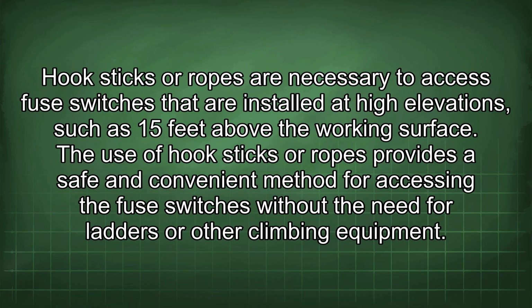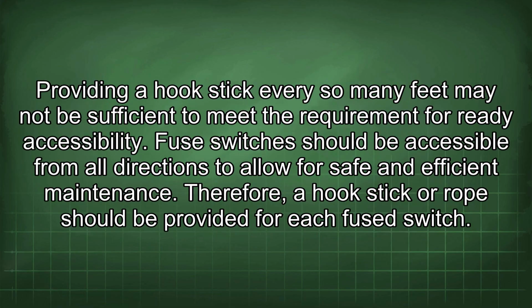The use of hook sticks or ropes provides a safe and convenient method for accessing the fuse switches without the need for ladders or other climbing equipment. Providing a hook stick every so many feet may not be sufficient to meet the requirement for ready accessibility. Fuse switches should be accessible from all directions to allow for safe and efficient maintenance. Therefore, a hook stick or rope should be provided for each fuse switch.